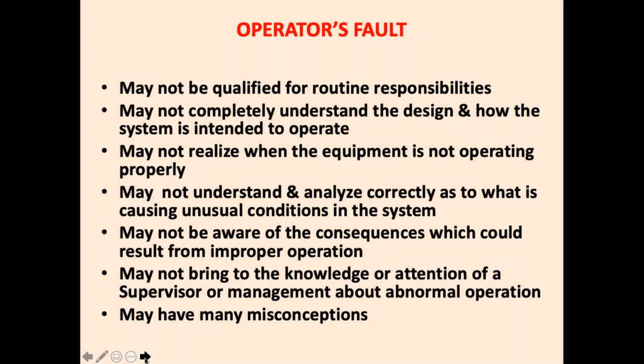Now, operator fault: he may not be qualified for routine responsibility. Many times the owner says, "Arey, this is my boy, he has no work, I will put him on the plant room operation." Yeah, it can be done, but he has to be trained thoroughly and he has to be qualified for routine responsibility. So he may not completely understand the design according to which the system is intended to operate. May not realize when the equipment is not functioning properly because he doesn't understand what is high discharge pressure, what is high discharge temperature, where the oil should be, etc., etc. May not understand and analyze correctly the causes which cause system problems. May not be aware of the consequences which could result from improper operation.